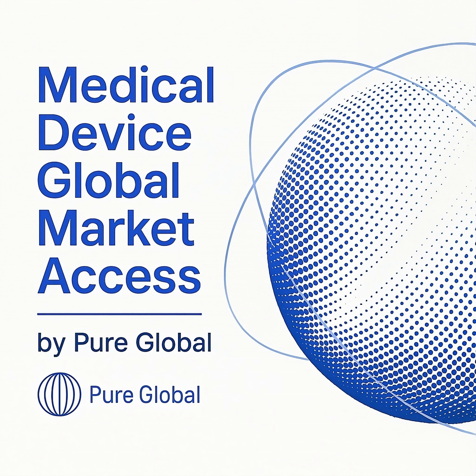Your App Store listing is no longer just marketing material. It is now an extension of your device's labeling. The intended purpose, indications for use, and user interface images you display must align perfectly with what is documented in your approved technical file. Any discrepancy can be interpreted as misleading advertising or off-label promotion, creating a significant compliance breach. Manufacturers must now treat their App Store presence with the same rigor as their instructions for use.